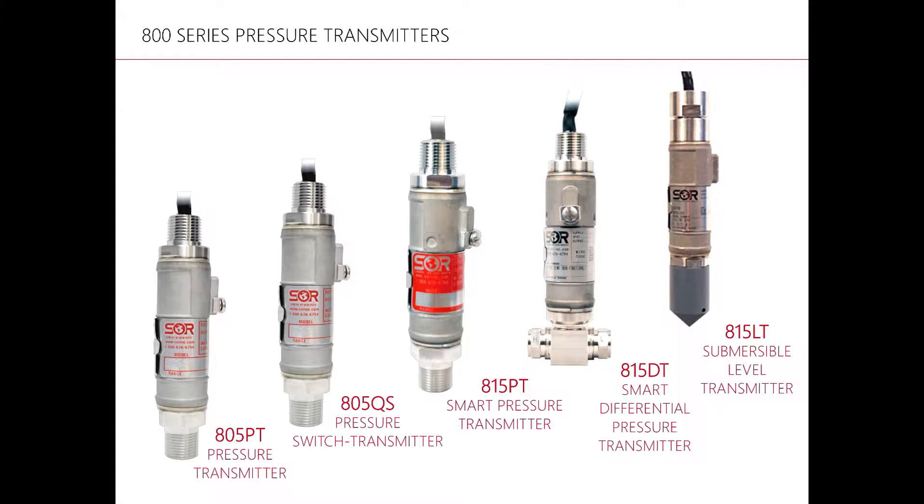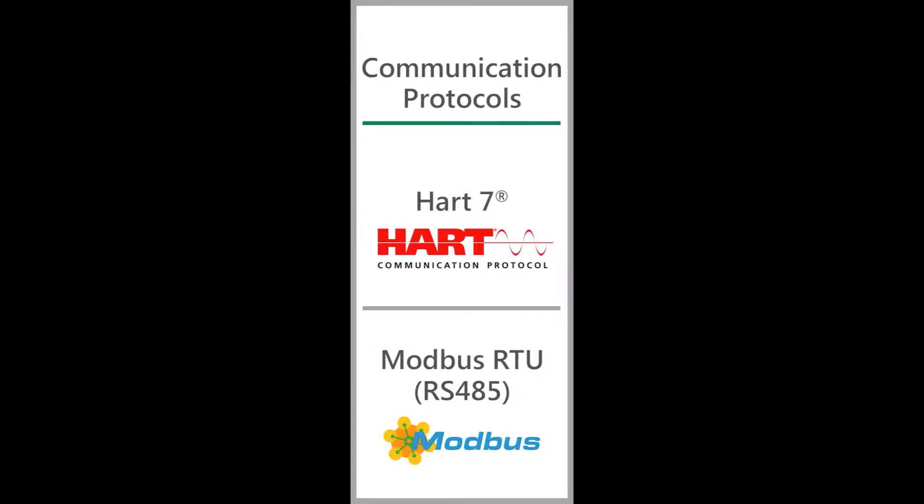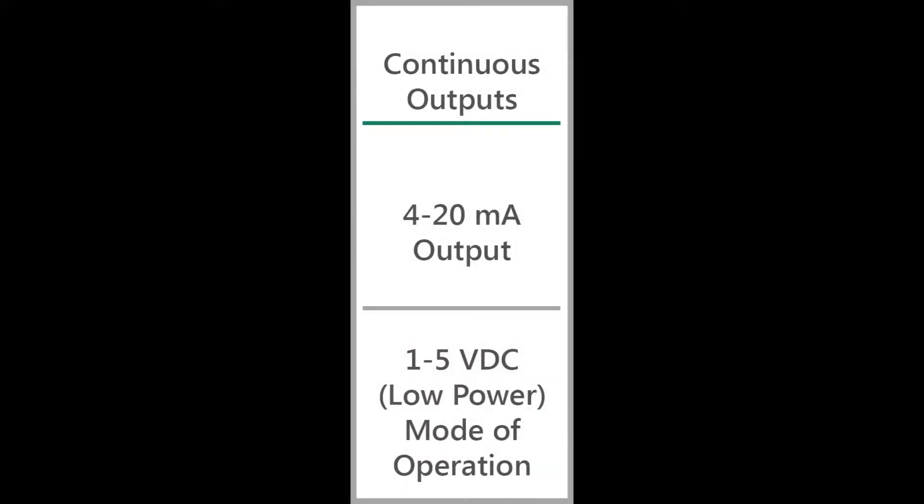The 815LT is actually the same transmitter as the 815PT except it is now submersible and has all the same great features and benefits. This includes HART communication protocol, Modbus RS-485 serial communications, 1 to 5 volt DC output, as well as 4 to 20 milliamp output. You get all these features whether you ask for it or not.